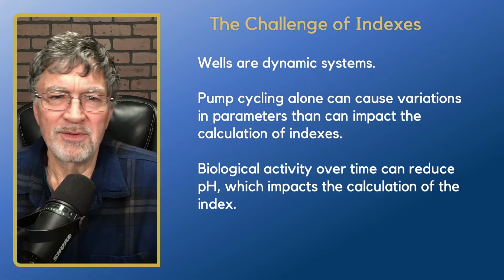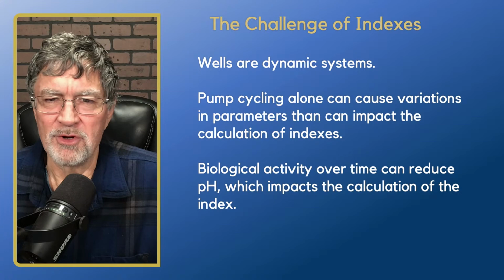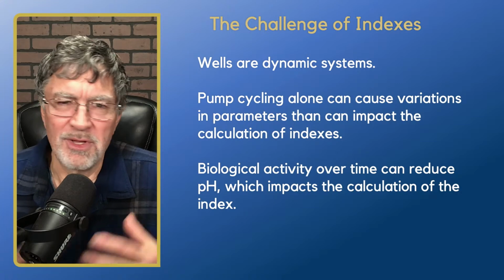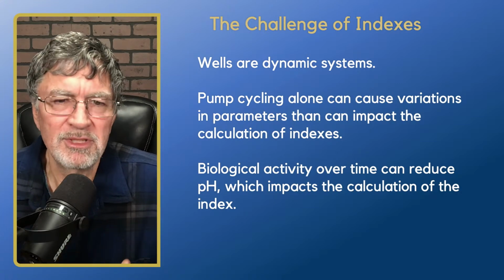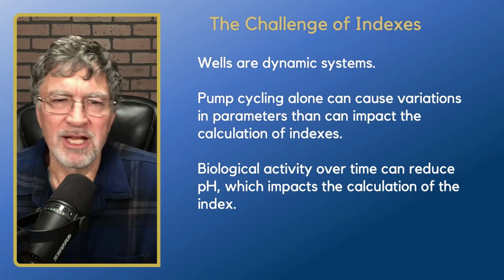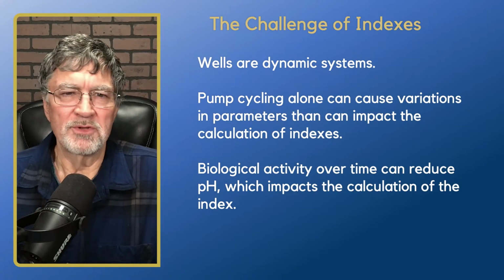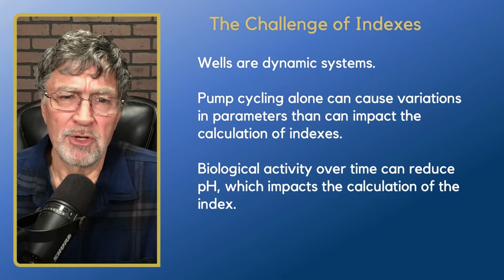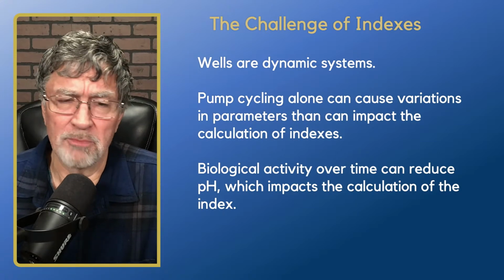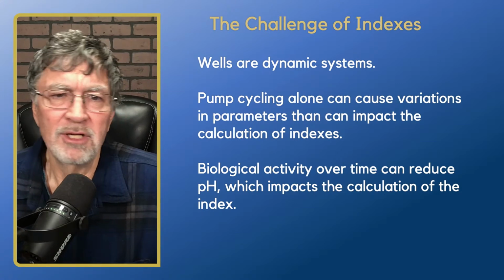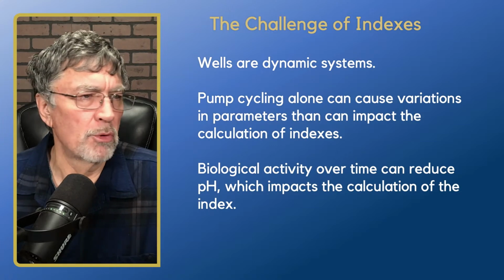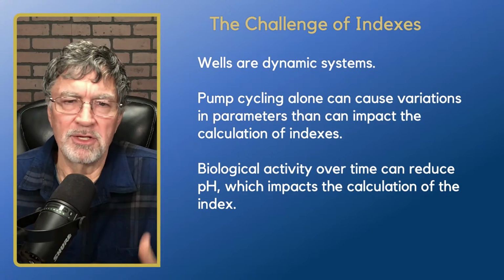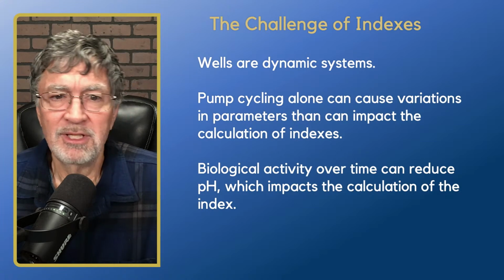So keep in mind that as a calculated index, there are 5 factors that go into the LSI calculation. If any of those change due to the dynamic part of the well system, then your LSI may not be quite as reliable. So that's why I say use it as a tool to give you an indication, but look at the other parameters. During the well health check process, we have the lab calculate all these different parameters, and we look at them all together in sum total, and that really helps us make a determination of what's actually going on down there.